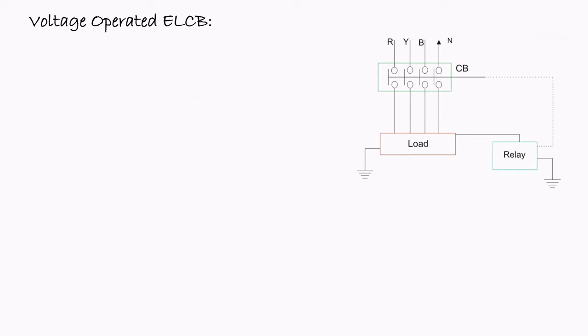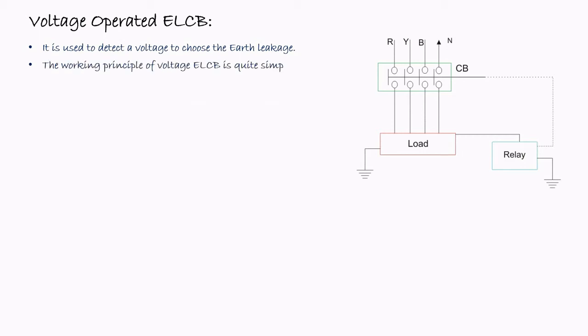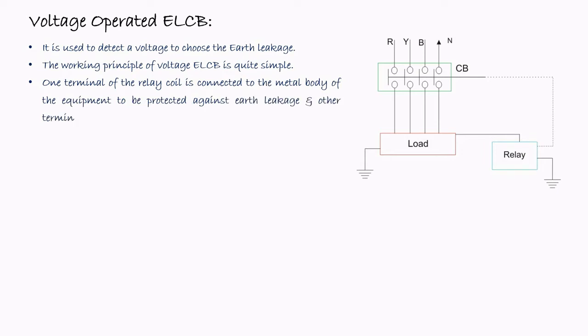So let's see the voltage operated ELCB. Here the circuit is shown with the voltage operated ELCB. It is basically used to detect a voltage to sense the earth leakage. The working principle of the voltage ELCB is very simple. Here, one terminal of the relay coil is connected to the metal body of the equipment to be protected against the earth leakage, and the other terminal is connected to the earth directly. So here it is shown. One side of the ELCB is connected to the load, and the other side is connected to the earth.